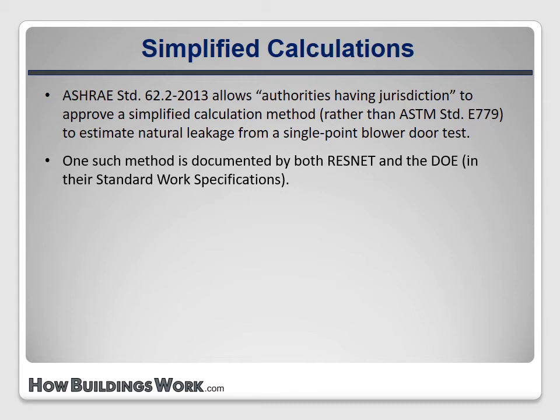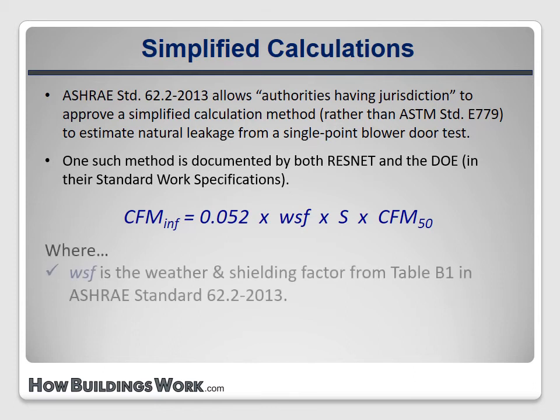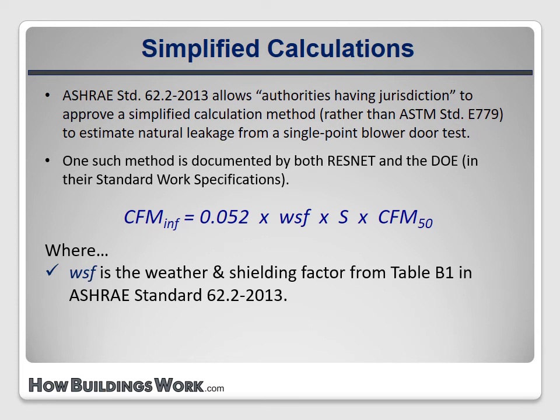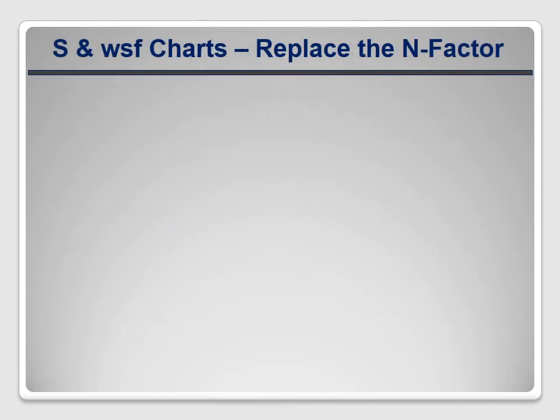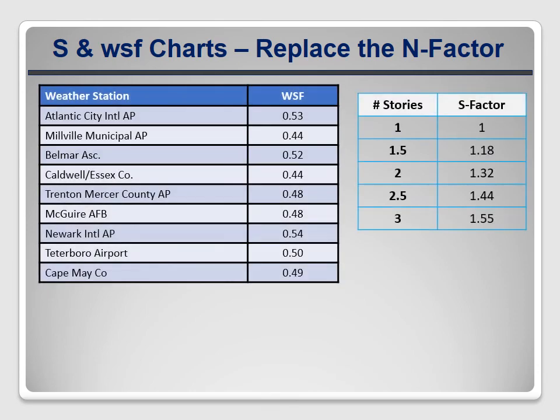In this lesson, I'll use the simplified calculation method. It states that the infiltration rate at natural conditions can be estimated as: CFM infiltration equals 0.052 times WSF times S times CFM 50. In this equation, WSF is the weather and shielding factor from table B1 of standard 62.2; S is a factor accounting for the height of the building from table X1; and CFM 50 is the blower door test result at 50 pascals. For our example house, the weather and shielding factor is 0.48, and the S factor is 1 because it's a one-story house. If it were two stories, the S factor would be 1.32.